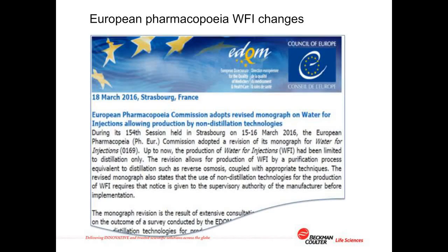Online monitoring, particularly for TOC and conductivity, have taken on an even greater significance since the European Pharmacopoeia adopted its revised monograph on water for injection in March of 2016, allowing for the first time the generation of water for injection from reverse osmosis.